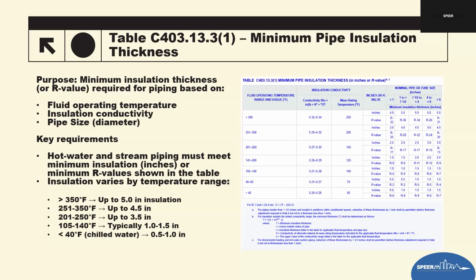Low temperatures such as chilled water or glycol systems below 40, insulation is required primarily to prevent condensation and maintain energy performance. Its requirement ranges from 1/2 inch to 1 inch depending on pipe size. And then R value versus the pipe size in inches. The table basically has 2 compliant pathways: insulation thickness or the R value. This allows flexibility in selecting the type of material that you're using. You're just looking for it to meet one or the other.